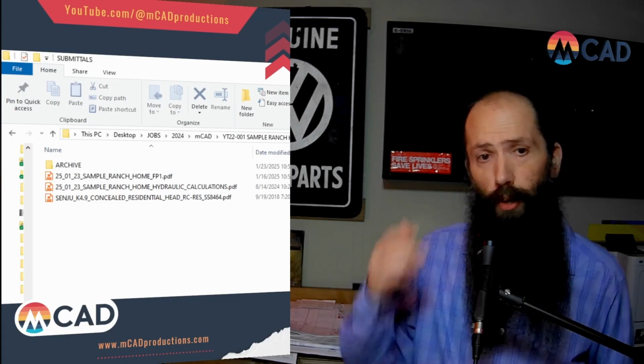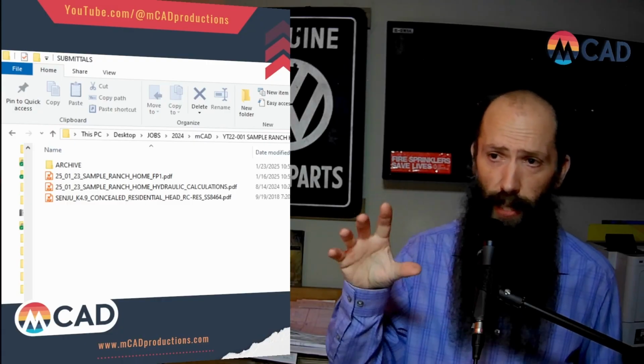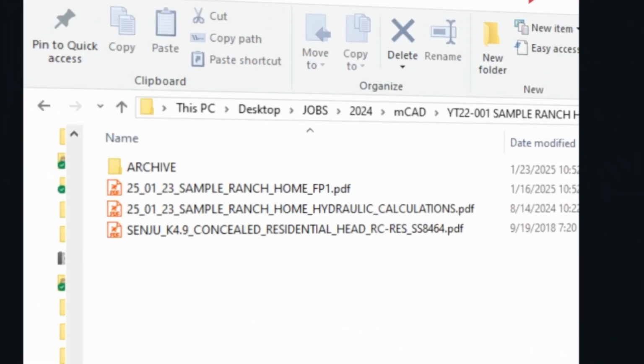All right. And so at this point through the MCAD system, the manager will take the last preliminary PDF from the technician and he or she will put it into the submittal folder that we created in our file organization structure. And so our final documents that we are giving to the contractor to submit go into this folder. We've got our plan, sample ranch home FP1, then we've got here our hydraulic calculations. And the last thing they need on a 13D system is the cut sheet for the sprinkler.